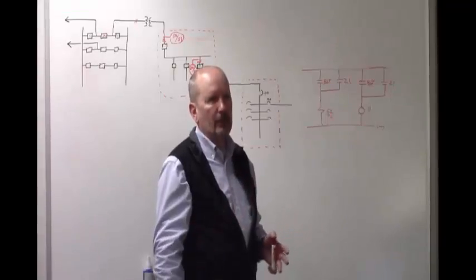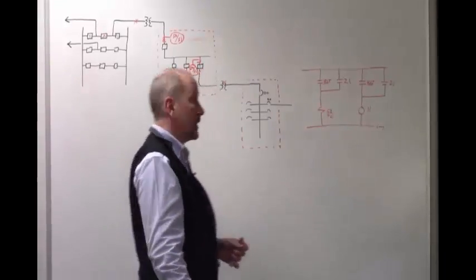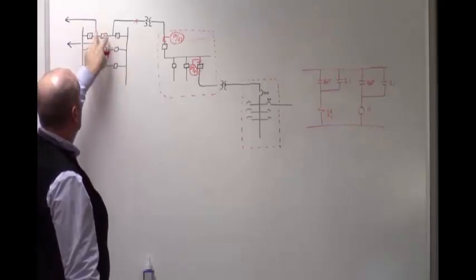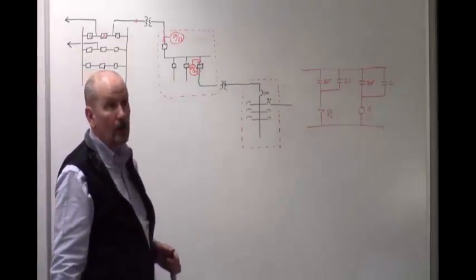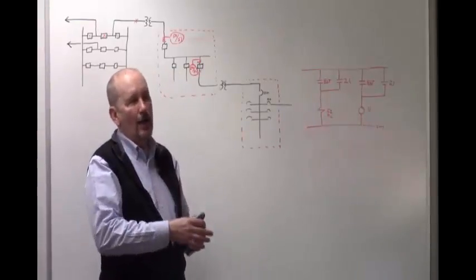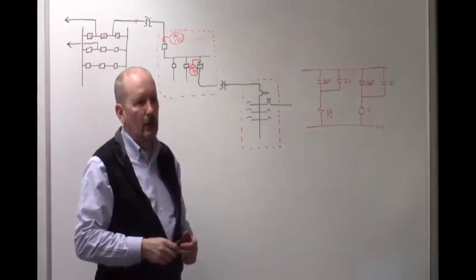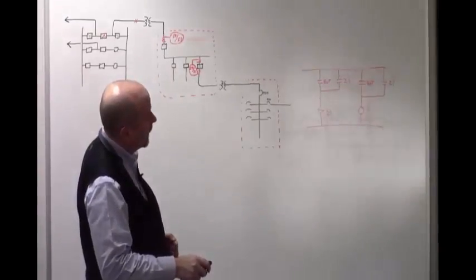Transfer trip can be done via fiber, phone line, tone, and other communication methods — we're going to cover all of that in a couple of classes. Protective trips initiate BFIs; control trips do not.